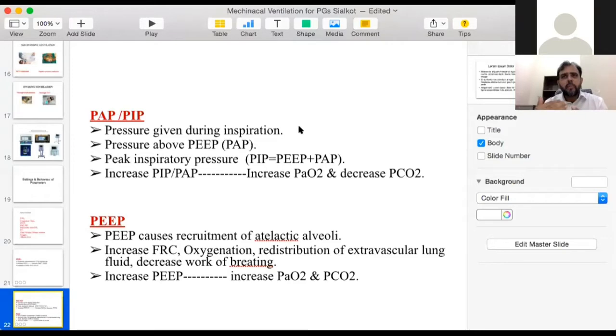So, peak inspiratory pressure and PEEP. PEEP is a constant pressure throughout inspiration and expiration, and PIP is over and above, a higher pressure that further inflates the airways. Increasing PEEP will increase the distensibility of the airways so that the PIP can be delivered easily. So PEEP will facilitate breathing. PEEP is a constant pressure.